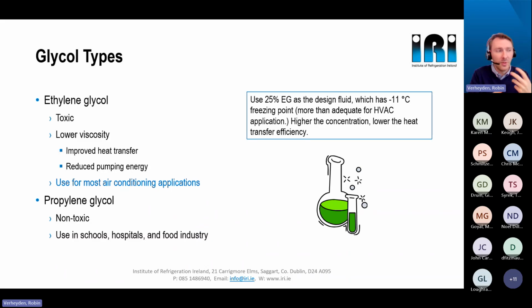Important to notice is that if you increase this percentage, the efficiency will drop very sharply after 35% of ethylene glycol. Always take into consideration that there is enough ethylene glycol in your water mixture to prevent freezing when building the ice, because then you need negative temperatures to make ice from water.